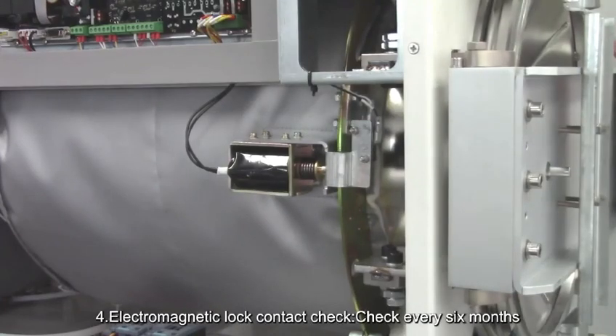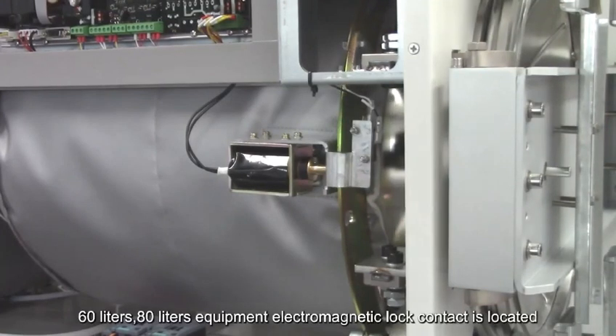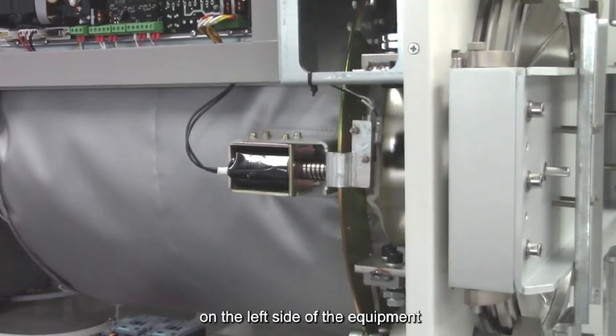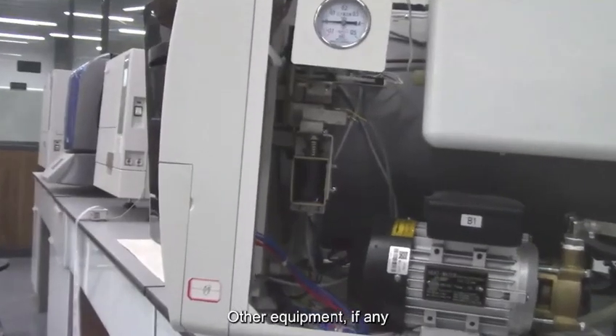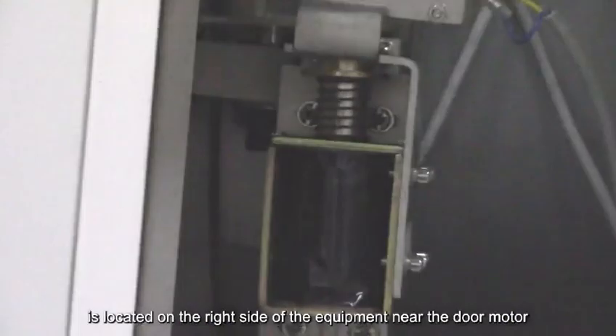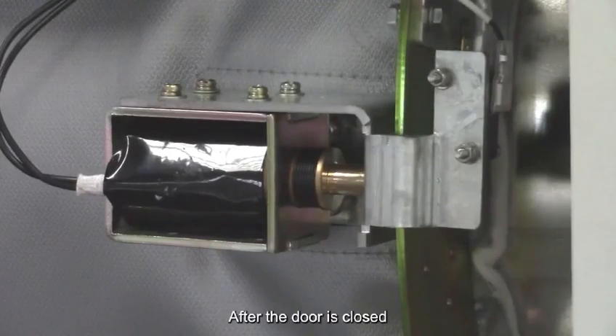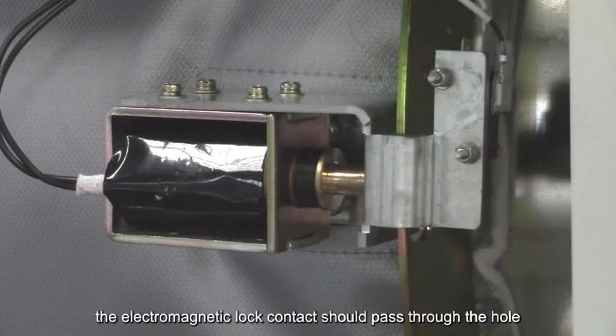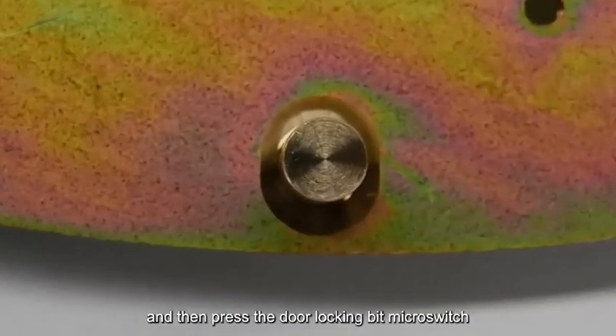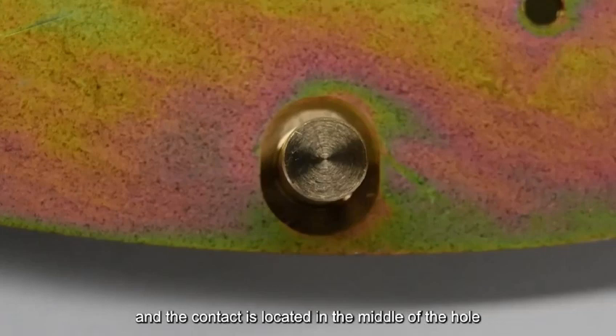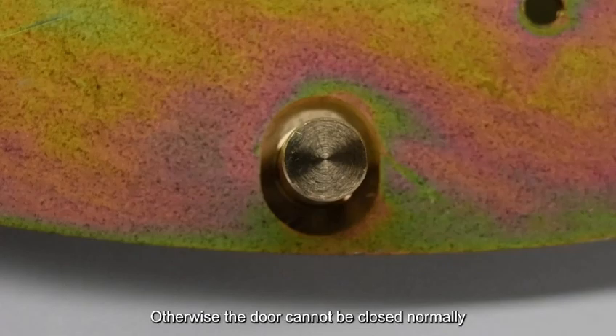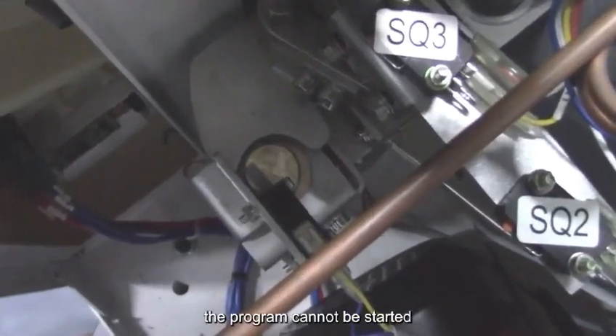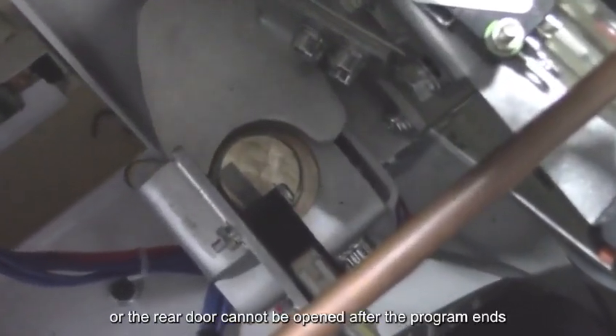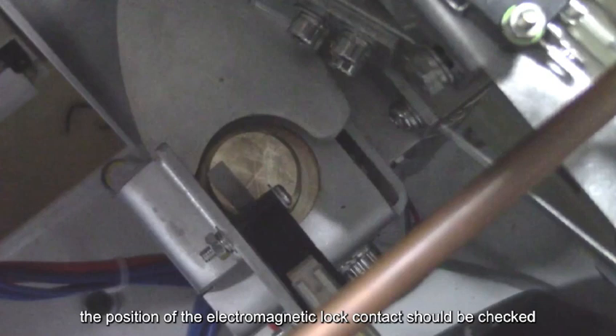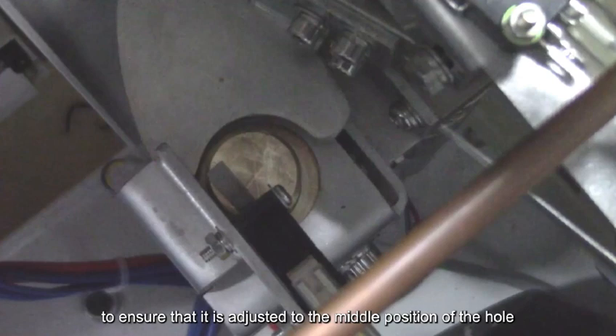4. Electromagnetic lock contact check. Check every 6 months. The 60 liters and 80 liters electromagnetic lock contact is located on the left side of the equipment. On other equipment, if present, it is located on the right side of the equipment near the door motor. After the door is closed, the electromagnetic lock contact should pass through the hole of the drive ring or stopper, and then press the door locking bit microswitch, and the contact should be located in the middle of the hole, not in contact with the sides. Otherwise, the door cannot be closed normally, the program cannot be started, or the rear door cannot be opened after the program ends. Therefore, the position of the electromagnetic lock contact should be checked and adjusted to the middle position of the hole.